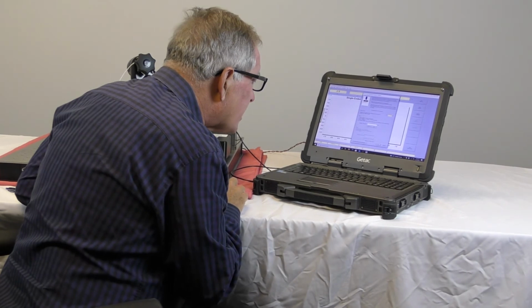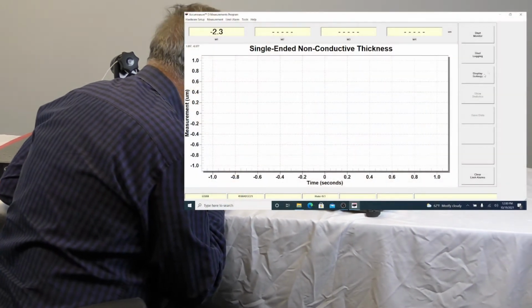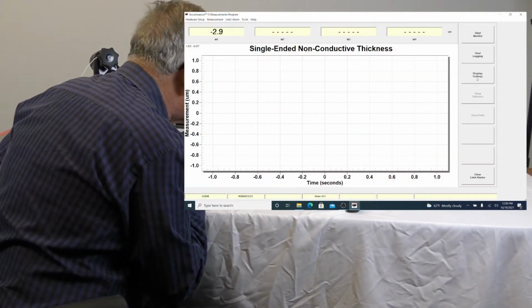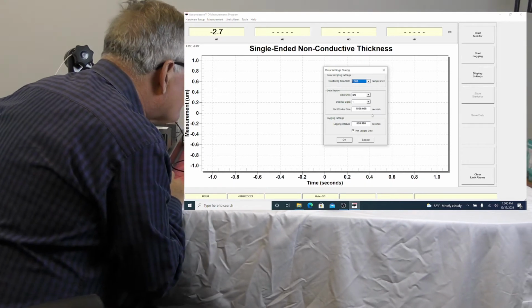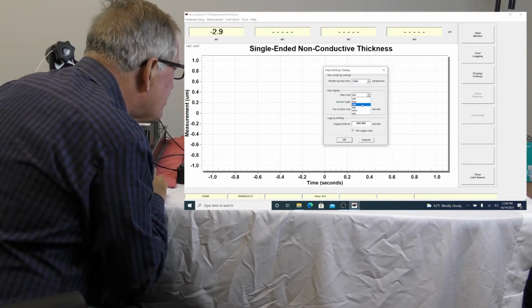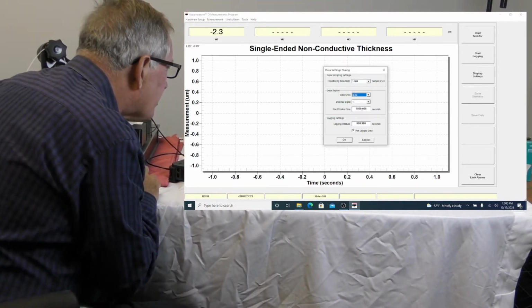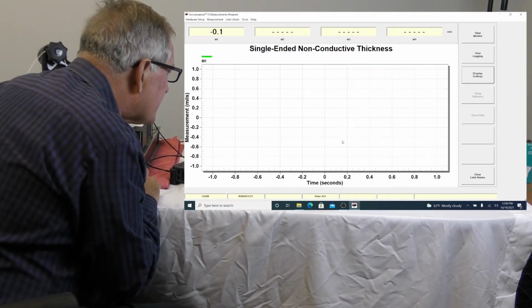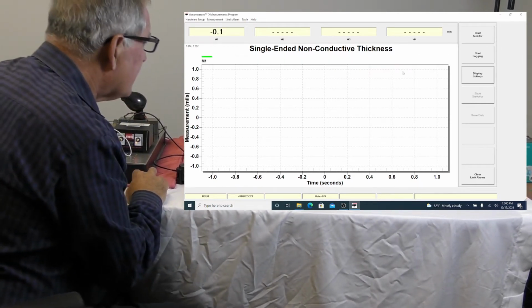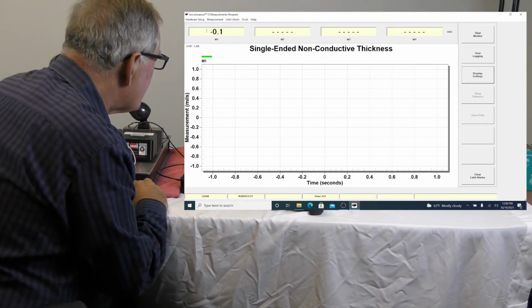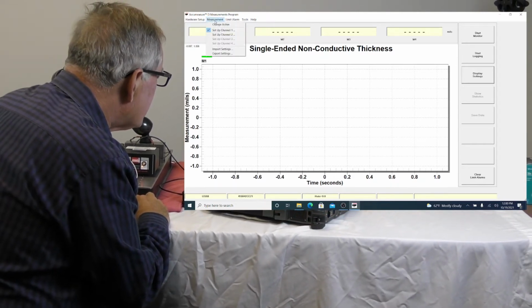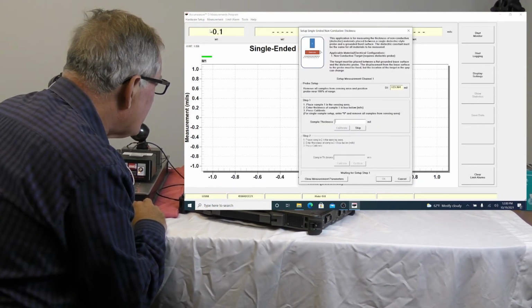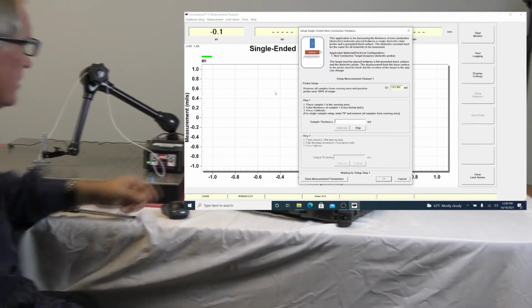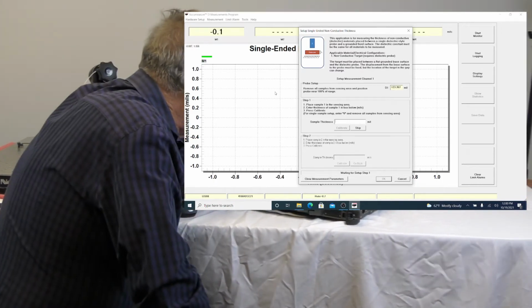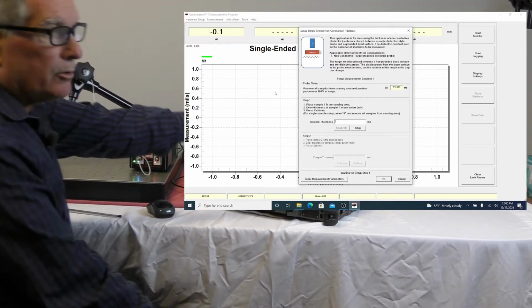but before we do that, I'm just going to change the engineering units here from microns to mils, or thousandths of an inch. So I've got that set in here right now, and then we go back to our measurements tab and set up channel 1. And we check and see our gap is at 123 mils, which is close to 3 millimeters.